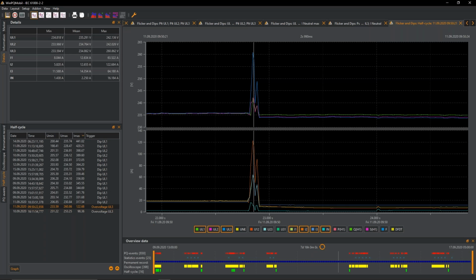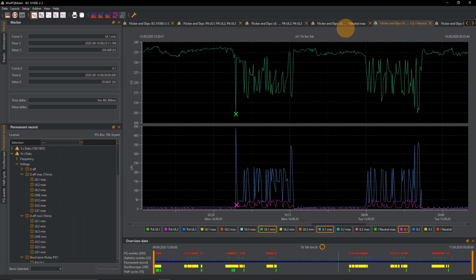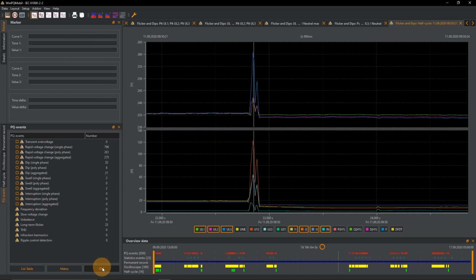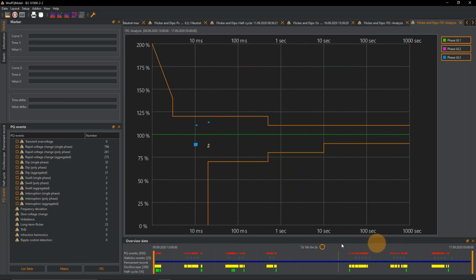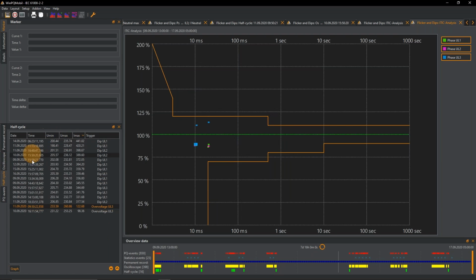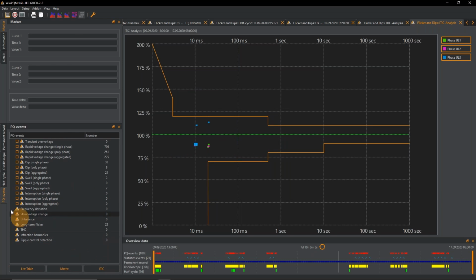So as a summary, the three ways to get to your fault record. First of all, the overview data with the oscilloscope triggers and the half cycle events. Here on the left side, you can see the number of events that took place in each category. The second one is the list on the left side, where you can filter for the maximum values of voltage and current and the category, of course. And last but not least, the ITIC curve, which can be found at PQ events and then clicking on ITIC. So these are the three easiest ways to get to your fault records.